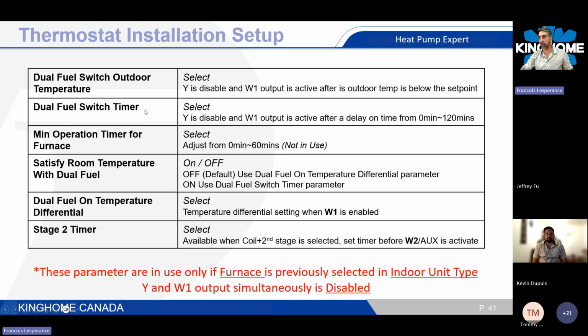Dual fuel switch timer, same stuff. You can put a timer, a time delay, before switching off the heat pump and turning on the gas furnace. Minimum operation timer for furnace. This one is not in use, so you don't have to do anything with this one, but it's meant to be just a delay to avoid short cycling. Okay.